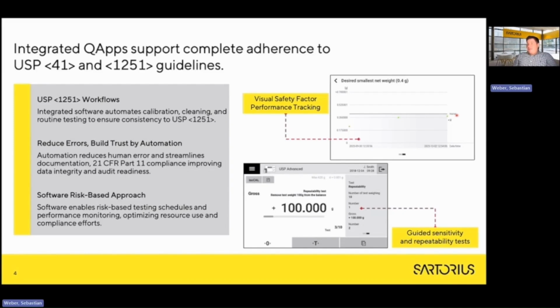You can see with this, okay, my results are well below the limit, so I can also reduce the safety factor. Or if I see I have a few results that are out of specification or very close to the limit, then I maybe have to think about putting in a higher safety factor. So with these tools, we give you guidance that helps you to evaluate your balance performance very easily, and based on this, also to adjust your safety factor.